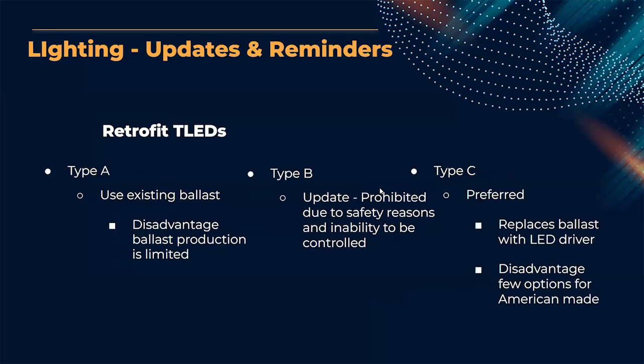So for retrofits continued, we have TLEDs, which are tubular LEDs. Type A uses the existing ballast. It's a short-term solution because ballasts are going away; they're not making them any longer. Type B is now prohibited in P100 due to safety reasons and the inability to control these lamps. So we prefer Type C, which uses an LED driver and a luminaire, which is very similar to an actual LED luminaire.